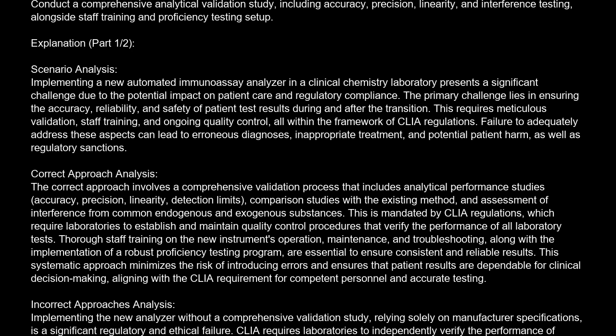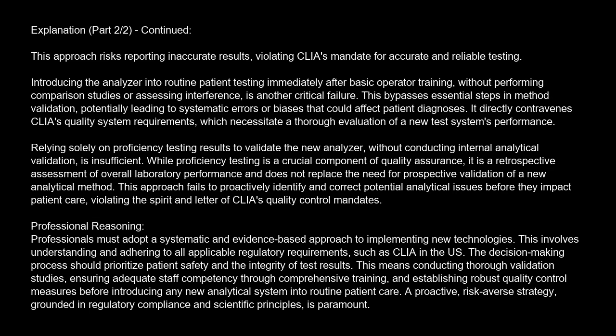Incorrect approaches analysis. Implementing the new analyzer without a comprehensive validation study, relying solely on manufacturer specifications, is a significant regulatory and ethical failure. CLIA requires laboratories to independently verify the performance of analytical methods before routine use. Manufacturer data alone does not satisfy this requirement, as it may not reflect the laboratory's specific operating conditions or patient population. This approach risks reporting inaccurate results, violating the CLIA mandate for accurate and reliable testing.